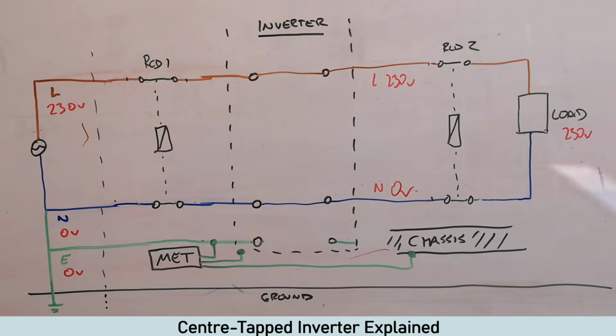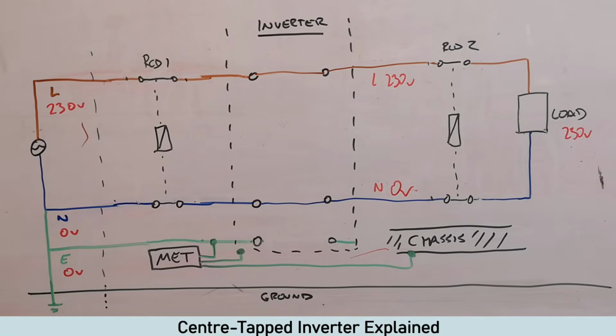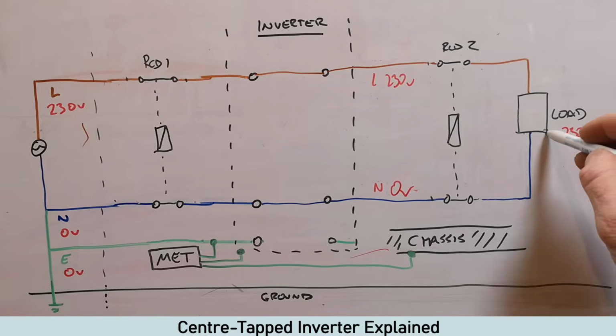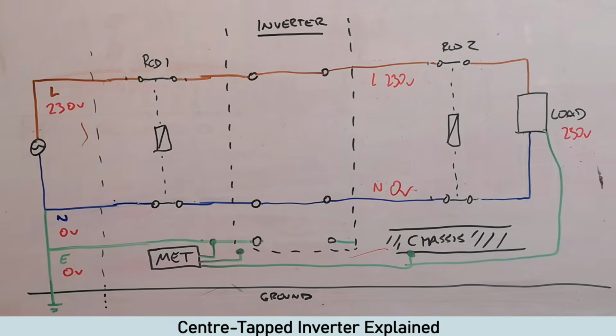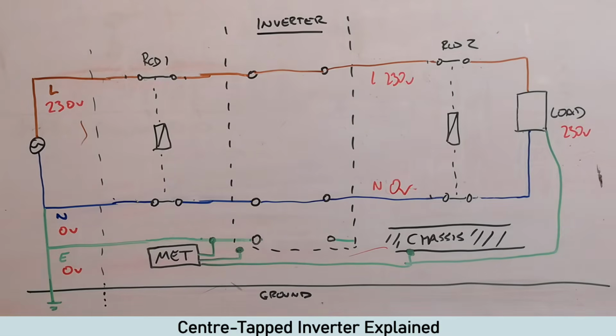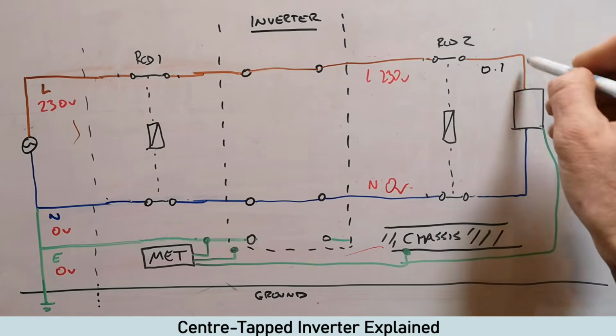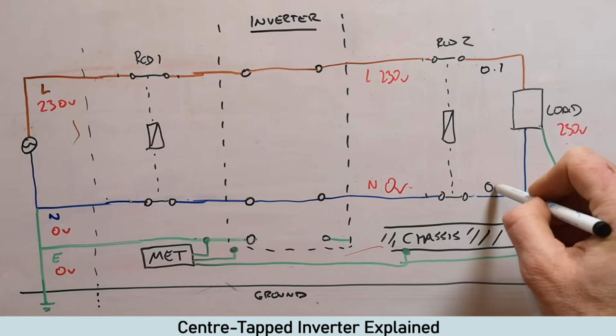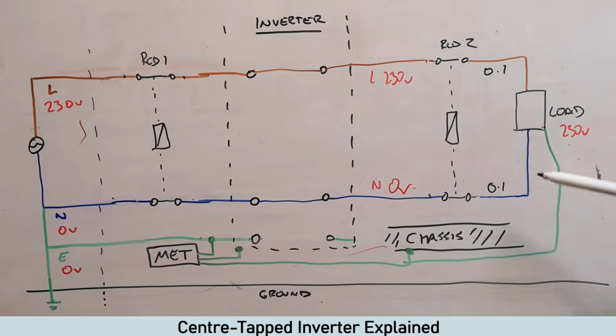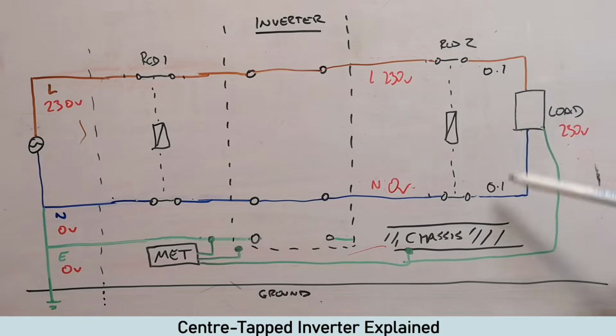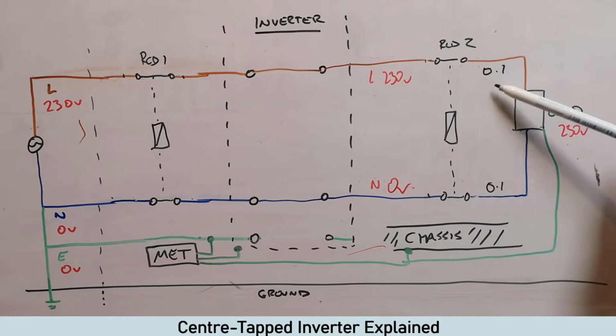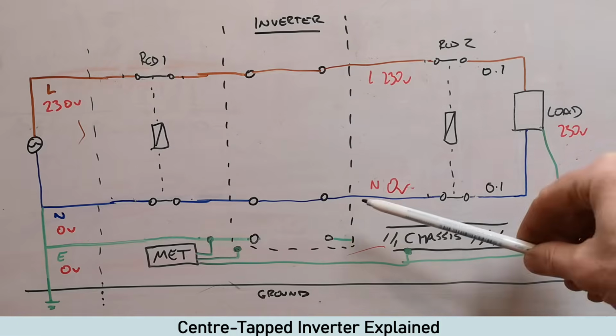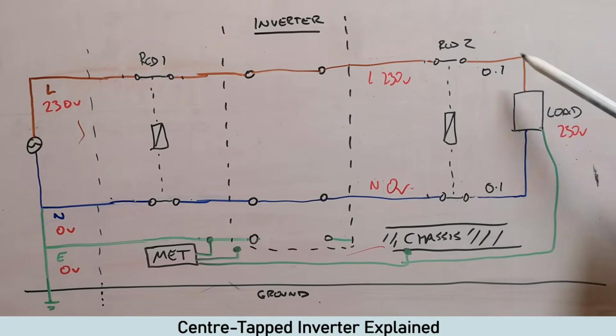This is what's happening now. The other earth I will put in actually is the earth from here. I'll just join it to there just to show you a path. So we've got an earth to our load there. An RCD is looking for balance. So coming out, if it sees 0.1, it wants to see 0.1 coming back in. Now these two figures I'm just using as a pure example, just to give you an idea. So 0.1 comes out, 0.1 back in, and it's more than happy to sit there all day.